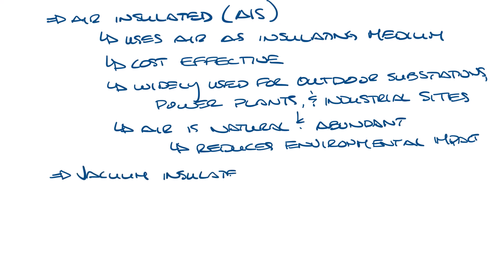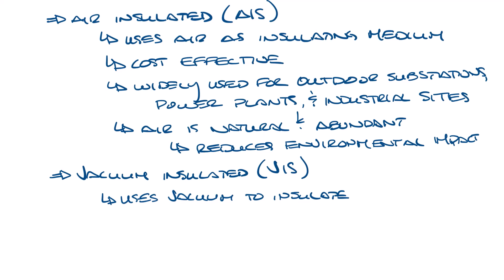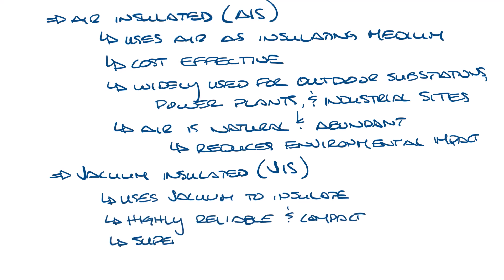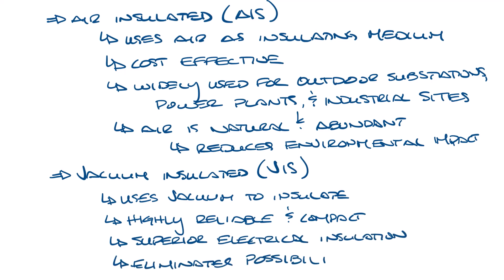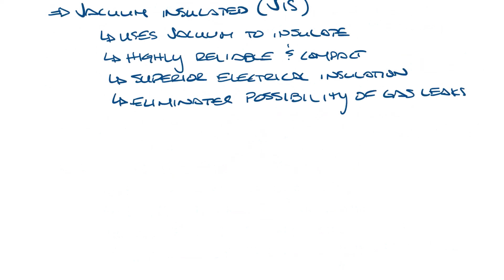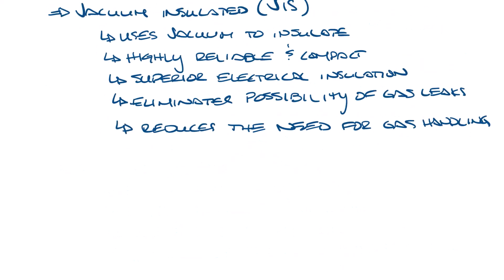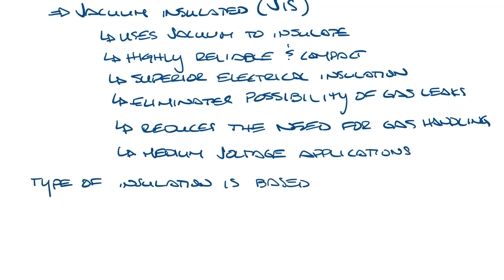And then we have vacuum insulated switchgear, VIS. This uses a vacuum environment to prevent arcing, making it highly reliable and compact. It offers superior electrical insulation properties and eliminates the possibility of gas leaks, reducing the need for gas handling procedures, which enhances safety. You'll see it in medium-voltage applications like commercial buildings and manufacturing plants. Each type of insulation is chosen based on space, cost, and environmental considerations.